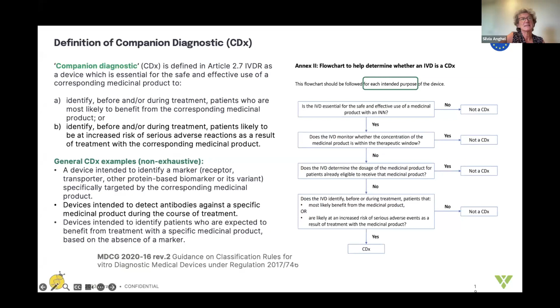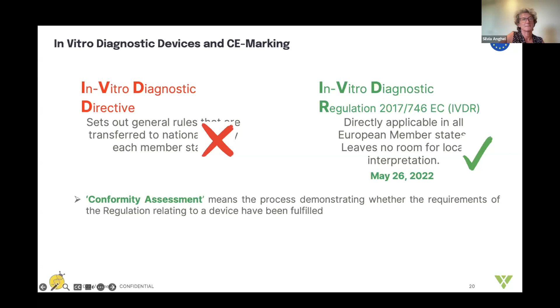IVD devices which are used in Europe must be CE marked. So CE marking means compliance with the requirements of the applicable regulation. In the case of in vitro diagnostic devices, we are talking about the in vitro diagnostic regulation, which is, as I said before, applicable in Europe since May 26, 2022. The process by which we demonstrate compliance to the requirements of the regulation, allowing CE marking of a device, is called conformity assessment. Next slide, please.